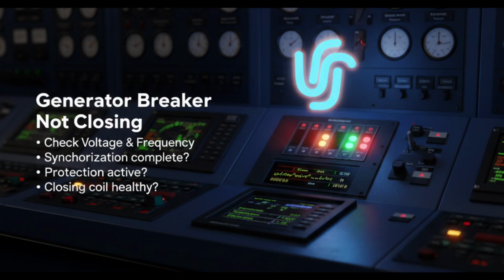Generator breaker not closing. Now let's discuss one of the most common problems, generator breaker not closing. When a generator is ready and synchronized, but the breaker still does not close, check the basics first. Is the voltage correct? Is the frequency matching the busbar? Is synchronization complete? If sync is incomplete, breaker interlock will prevent closing. Next, check protection relays. Is there any active trip signal? Overcurrent? Reverse power? Then check control power supply. Sometimes the breaker closing coil does not get power due to a blown fuse. Mechanical interlock can also block breaker operation. Do not keep pressing the close button repeatedly. That can damage the mechanism. Systematic checking saves time and avoids further problems.